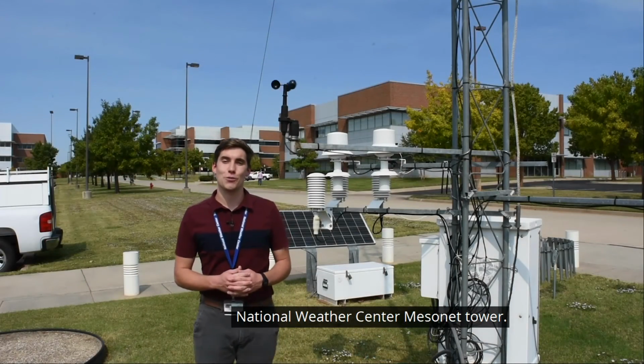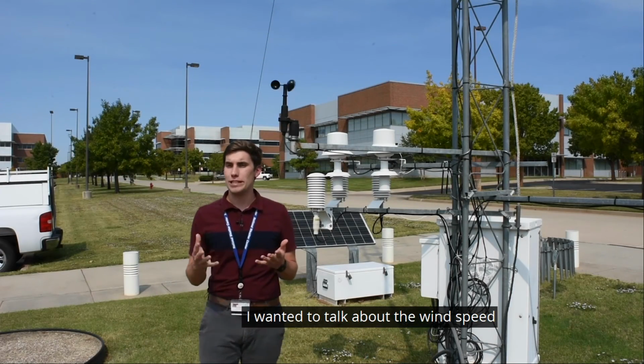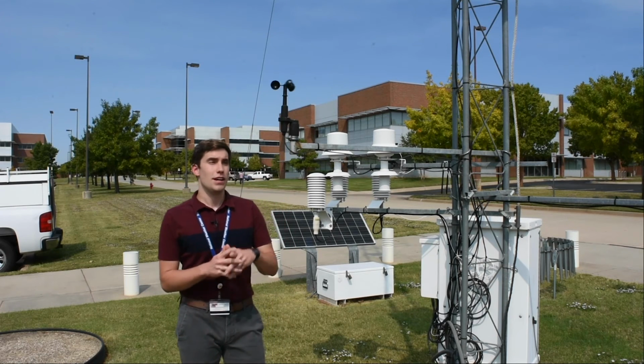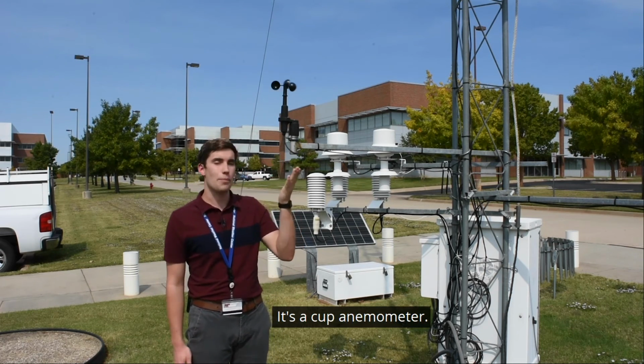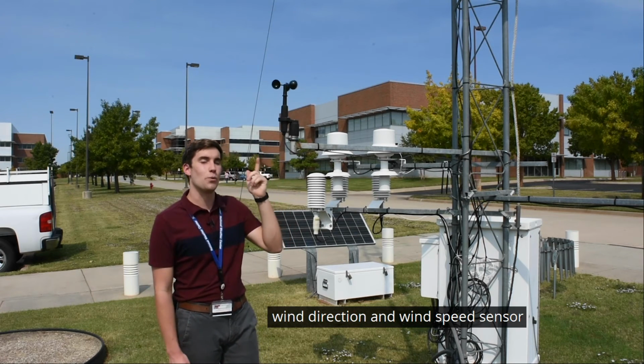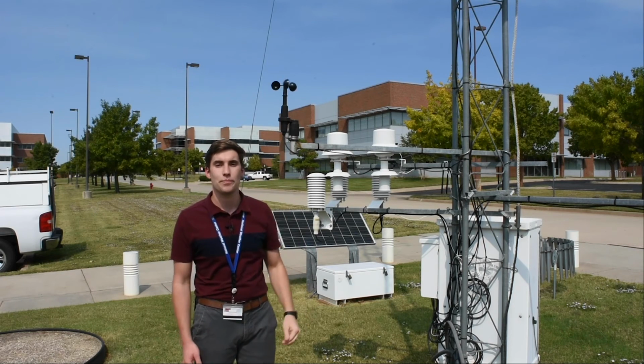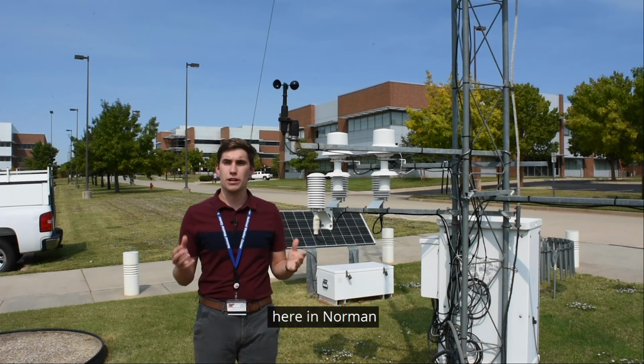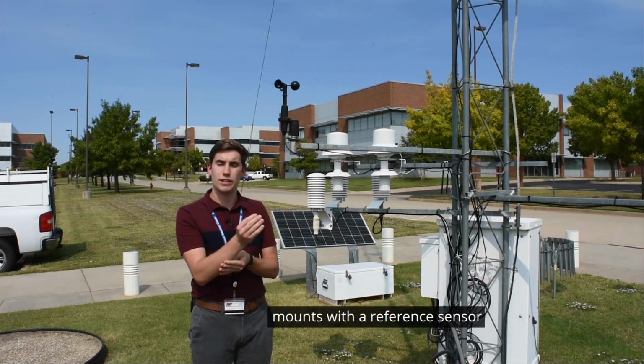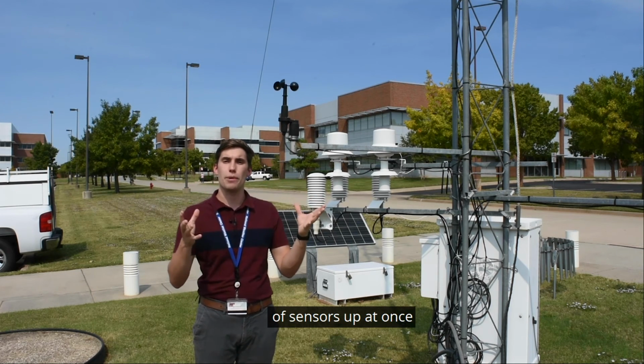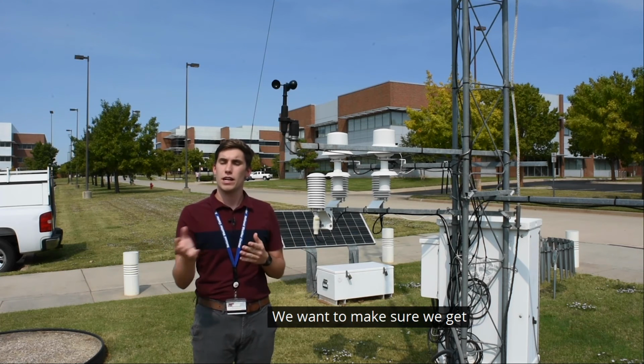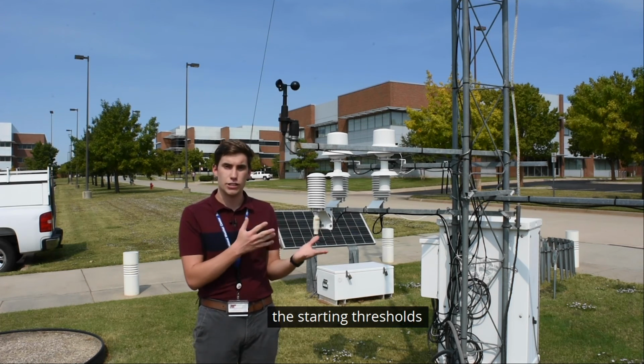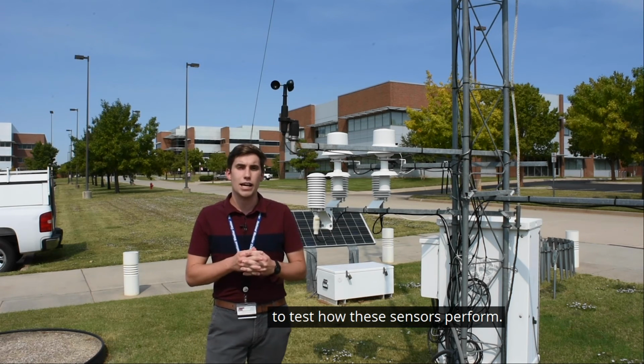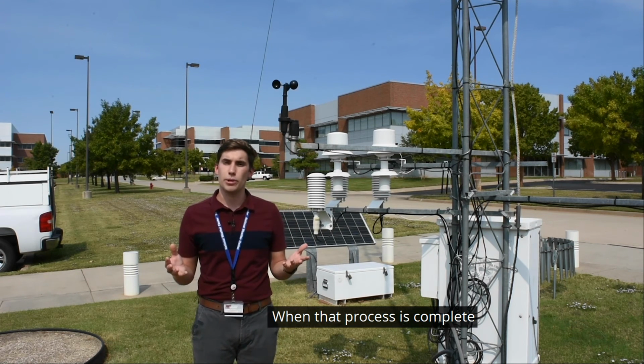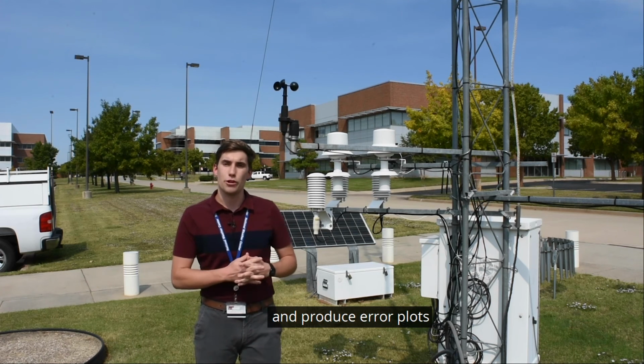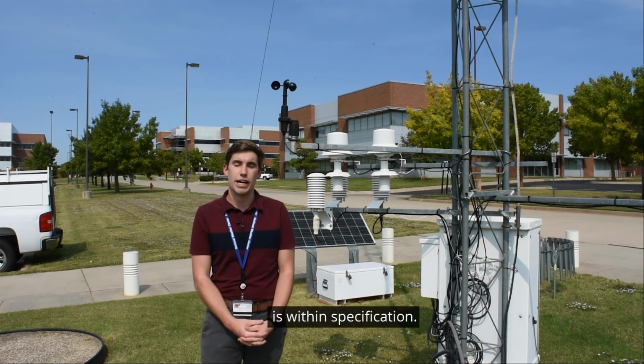We're back outside at the National Weather Center Mesonet Tower. I wanted to talk about the wind speed observations we take here at the Mesonet. This is an example of our 2-meter wind speed sensor. It's a cup anemometer, but we also have a 10-meter wind direction and wind speed sensor above me. We calibrate these sensors here in Norman with a bunch of different mounts with a reference sensor in the center. So we'll put a bunch of sensors up at once, let them go for about 2 weeks. We want to make sure we get some calm winds to test the starting thresholds, along with some stronger winds to test how these sensors perform. When that process is complete, we bring them back to the National Weather Center and produce error plots to make sure that data is within specification.